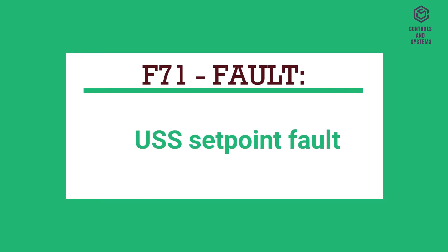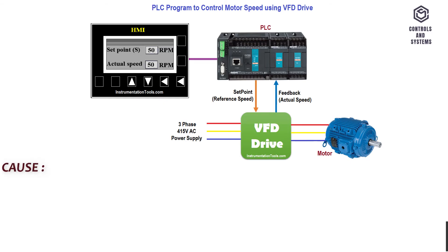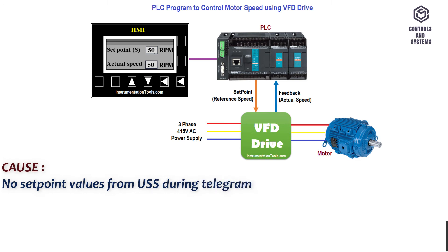F71 Fault: USS Setpoint Fault. Cause: No setpoint values from USS during telegram off time. Remedy: Check USS master.